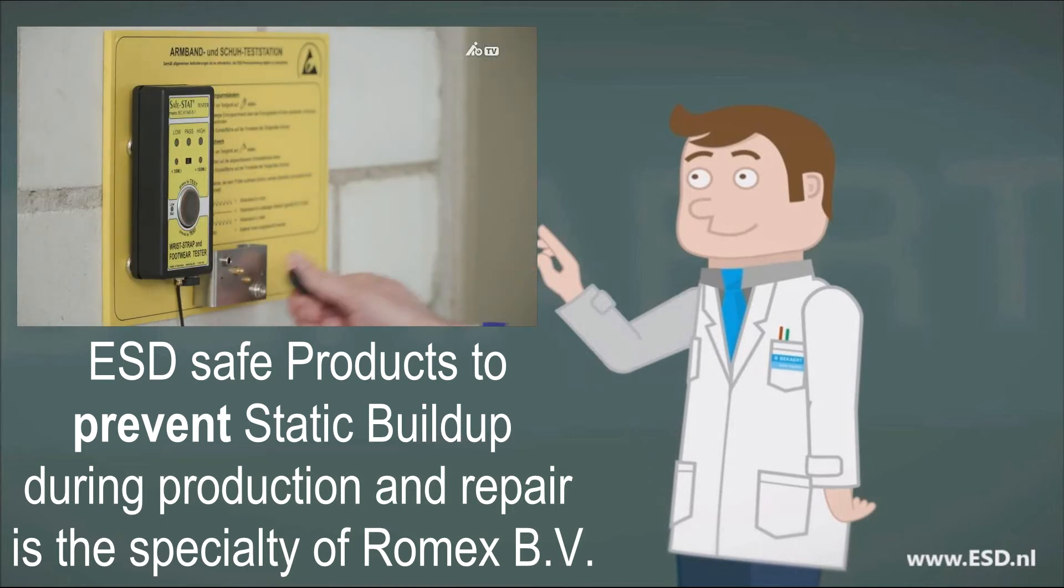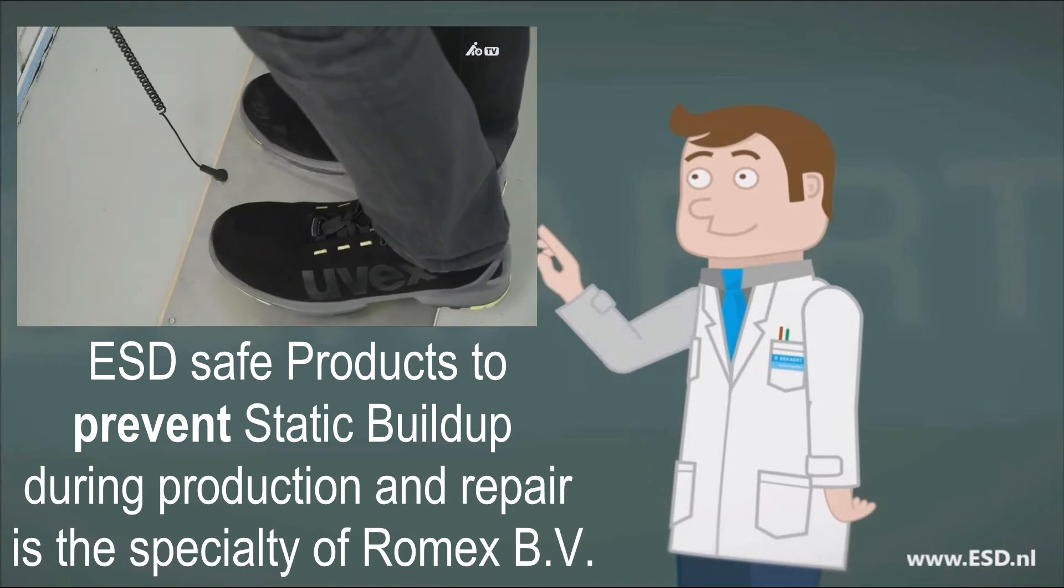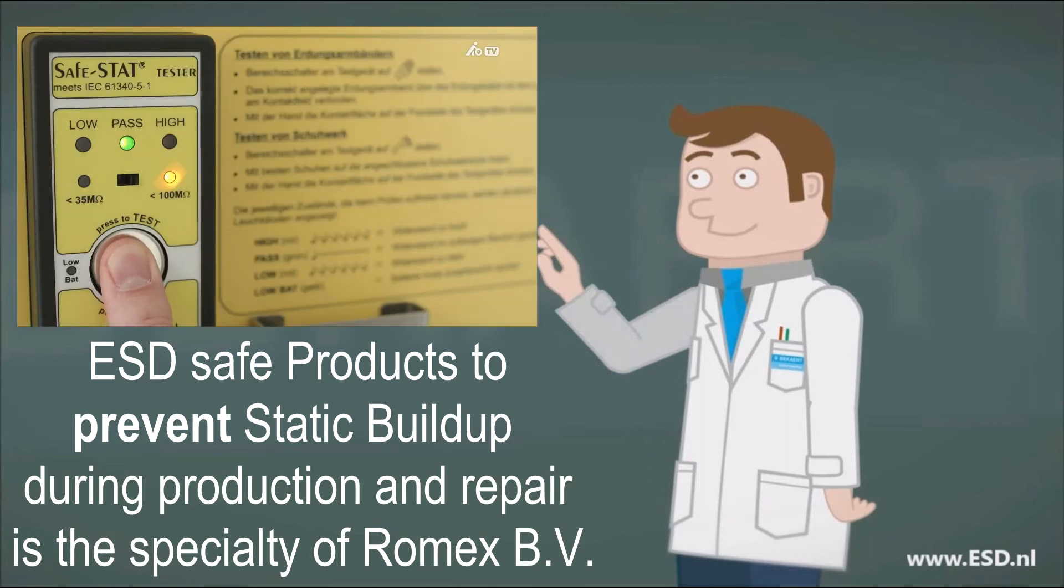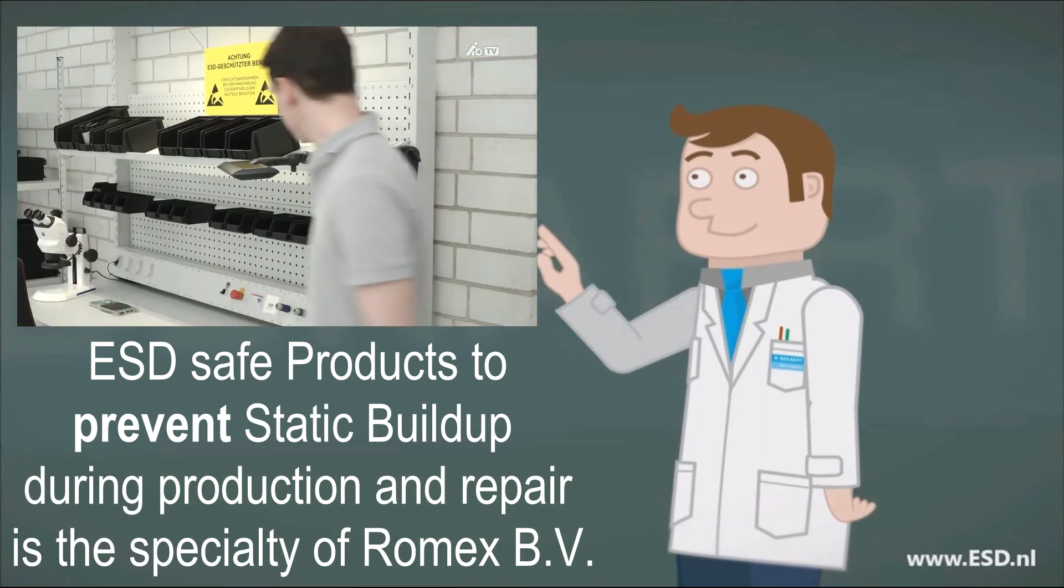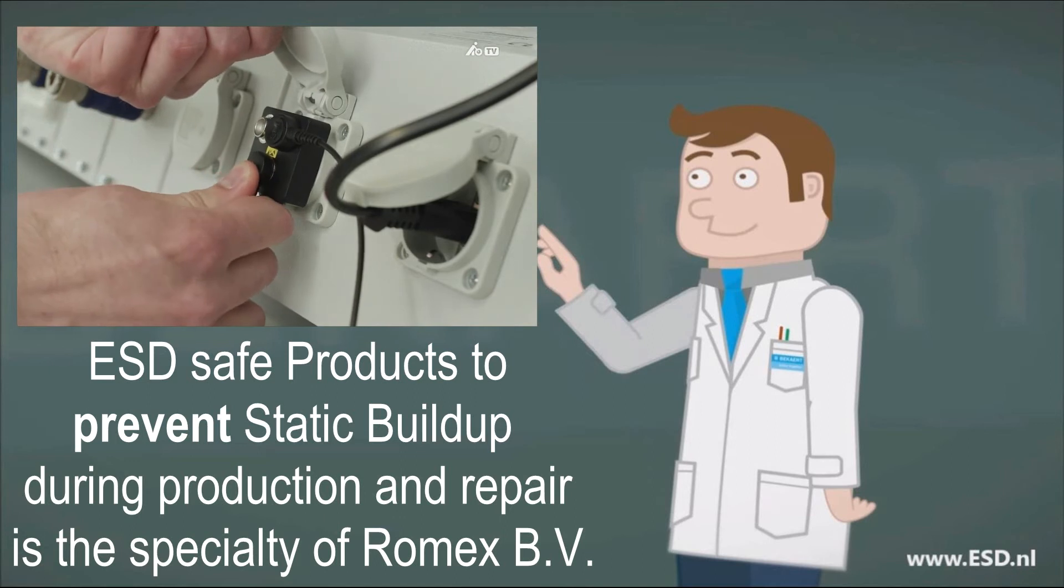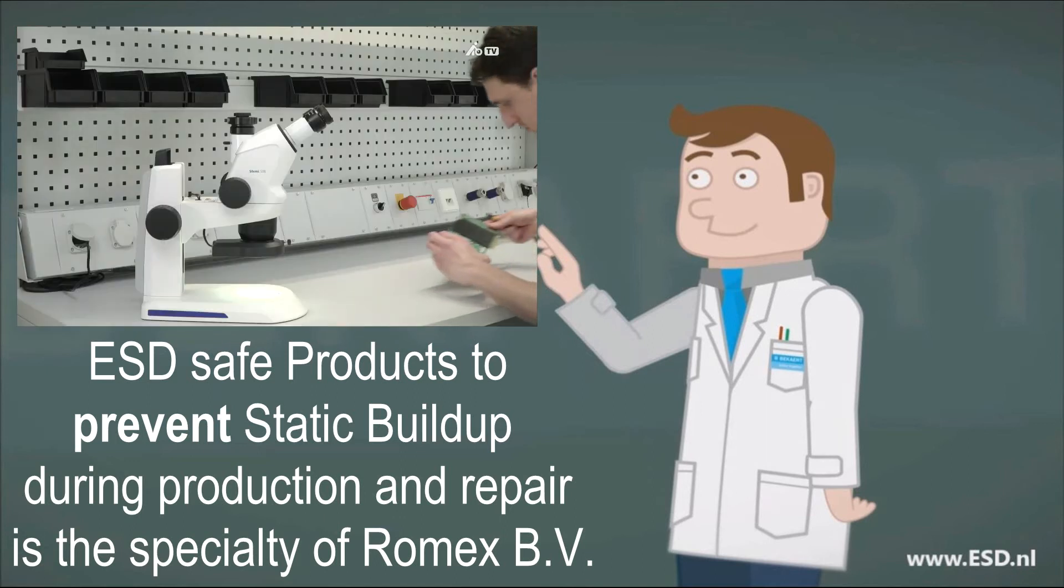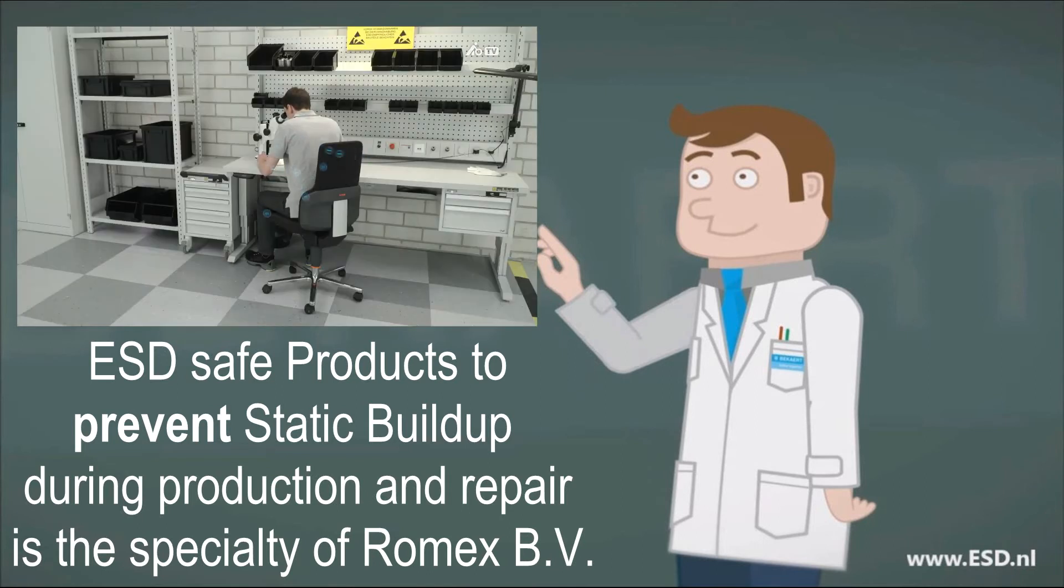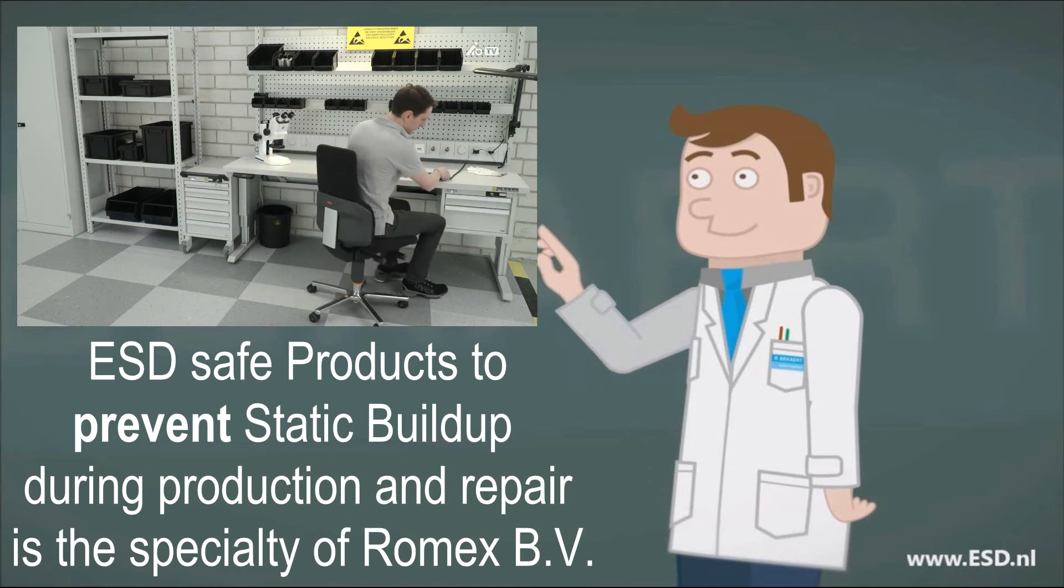Personal ESD protective workwear has to be checked every day before entering the EPA to ensure it's working correctly. If it is, the employee may enter the EPA and start work. After connecting the wrist strap to a grounding component, the electrostatic charge is slowly dissipated via the work surface and the grounding cable so the workstation stays charge neutral.